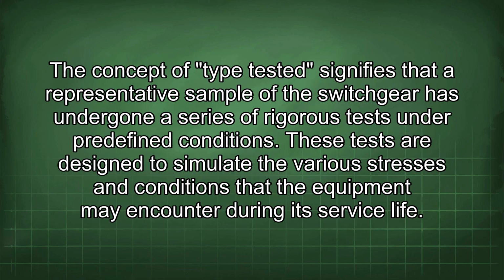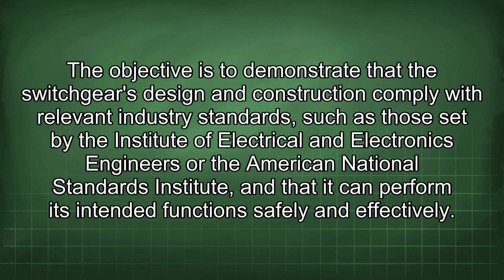The concept of type tested signifies that a representative sample of the switchgear has undergone a series of rigorous tests under predefined conditions. These tests are designed to simulate the various stresses and conditions that the equipment may encounter during its service life. The objective is to demonstrate that the switchgear's design and construction comply with relevant industry standards, such as those set by the Institute of Electrical and Electronics Engineers or the American National Standards Institute, and that it can perform its intended functions safely and effectively.